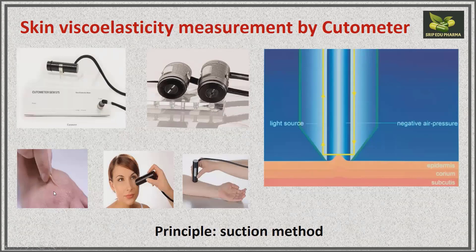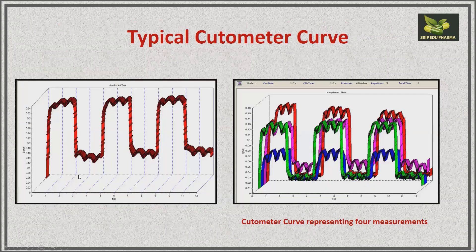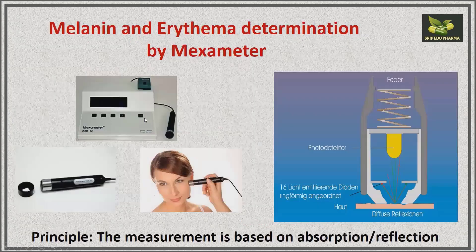With the cutometer, skin viscoelasticity of any body part can be observed. A light source is used and negative air pressure is applied, causing the epidermis to be sucked inward, allowing you to observe the elasticity and firmness of the skin. This is the typical cutometer curve obtained by the instrument — four measurements produce four curves, and readings are also available in an Excel sheet.